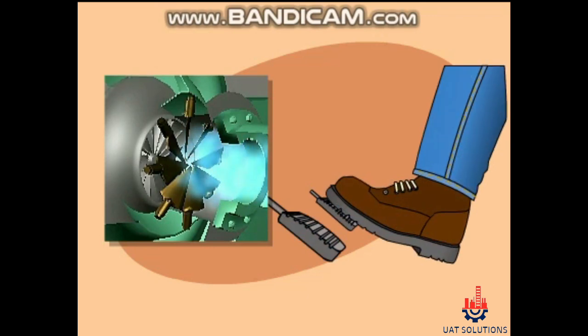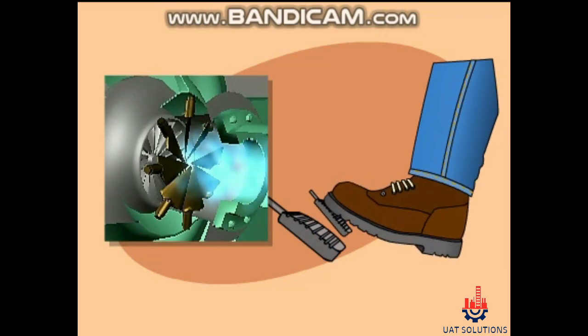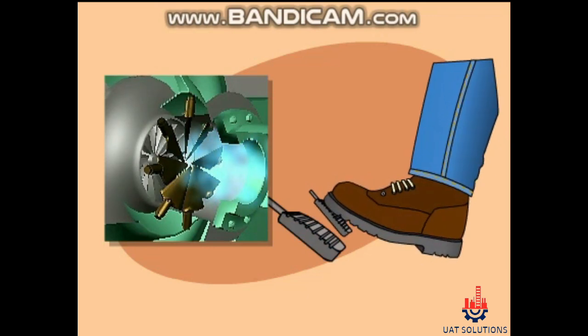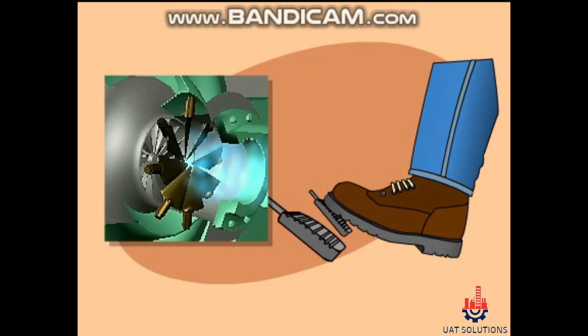On our constant speed chiller, the pre-rotation vanes have the same effect as the gas pedal. They restrict the gas flow to the compressor, while the compressor continues to operate at full speed — or, as our car analogy shows, full throttle.